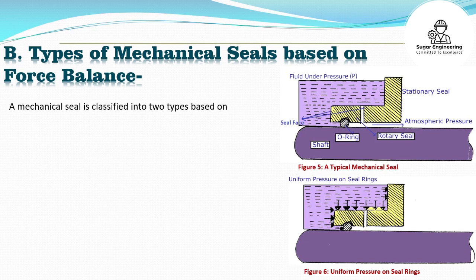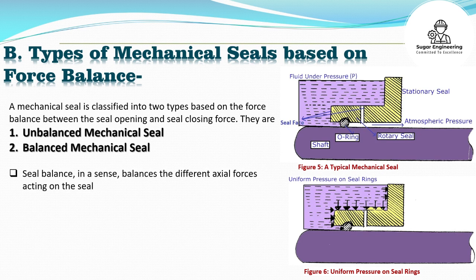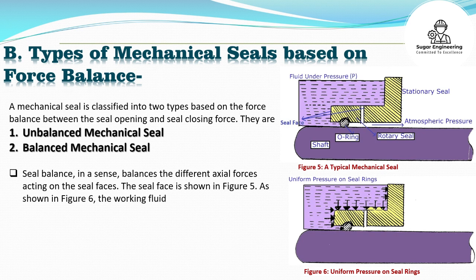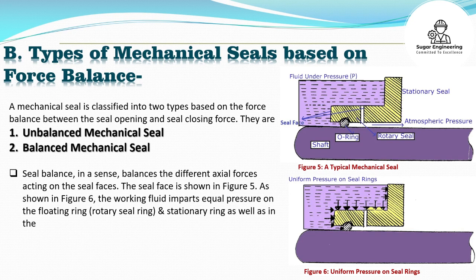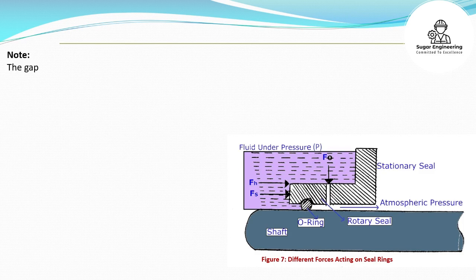Types of mechanical seals based on force balance: A mechanical seal is classified into two types based on the force balance between the seal opening and seal closing force. They are: unbalanced mechanical seal and balanced mechanical seal. Seal balance balances the different axial forces acting on the seal faces, as shown in Figure 5. As shown in Figure 6, the working fluid imparts equal pressure on the floating ring, rotary seal ring, and stationary ring as well as in the seal contact zone. Since the fluid pressure is identical, the load across the seal face depends on the area normal to the fluid pressure.